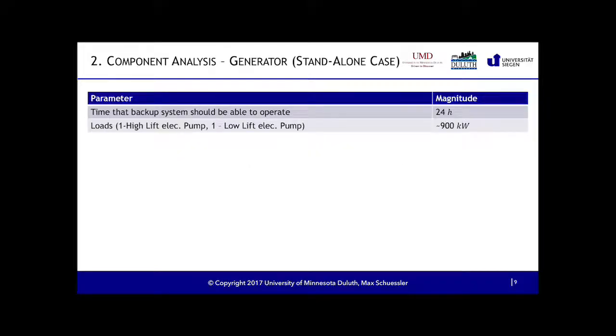And the generator tackles the resilience goal of my whole hybrid energy system. So I need to know what load I actually have to back up. After talking to the engineering office here, they said, okay, we actually only need the pumps 1, the high and the low lift pump 1, to run at a time, because we could have measures where the city is prohibited from using too much water. It should be sufficient in an emergency to run the pumps 1, which leads to 900 kW of constant load. And the worst outage the city has seen so far is 12 hours. So I said, okay, I'll look for a scenario where I can back up the system for 24 hours and which sizes of generator I need for that.